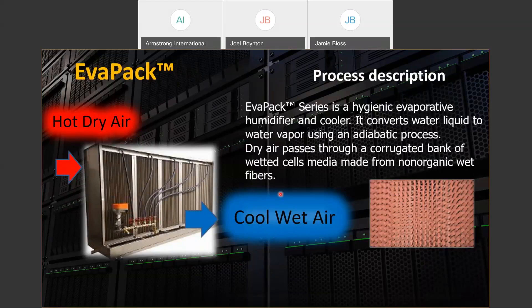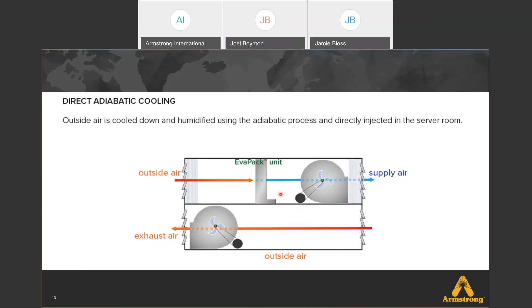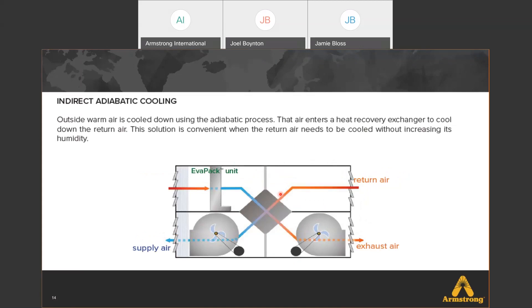There are two different types of adiabatic cooling. The first is direct adiabatic cooling: outside air is cooled down and humidified using the adiabatic process — in this case our EvaPack™ unit — and then directly injected into the server room. The second is indirect adiabatic cooling, where outside warm air is also cooled down using the adiabatic process, then that air enters a heat recovery exchanger to cool down the return air. This solution is convenient when the return air needs to be cooled without increasing its humidity. EvaPack™ brings in outside air and mixes it with return air to not add humidification as strongly as direct cooling would.